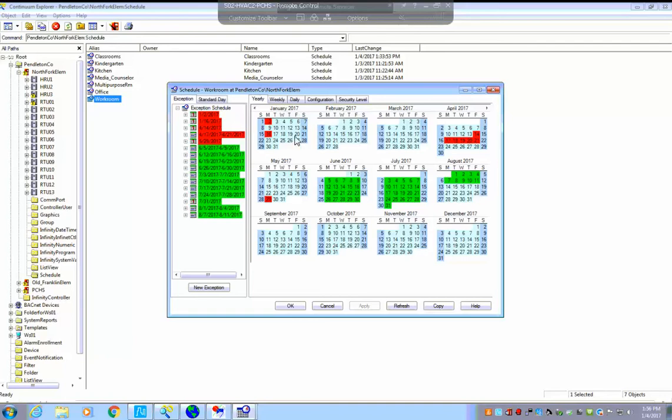What it does is change all the holidays, these exception days, to be exactly the same as what you had in your other schedule. The thing that is probably problematic for you guys is that the standard weekly day also changes. Those were 2:30 p.m. to 5 something, I forget what they were, but these are now exactly the start-stop times of the classroom schedules. So not only does it do the holidays, it also does the weekly schedules. So those change. I don't know of a way to only do the holidays or only the weekday schedules. It's kind of all or nothing.